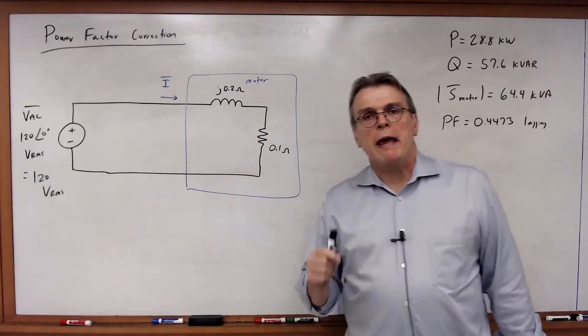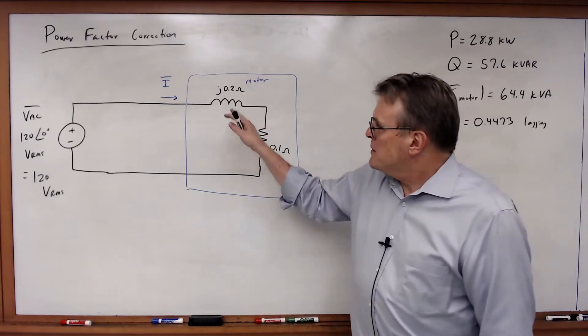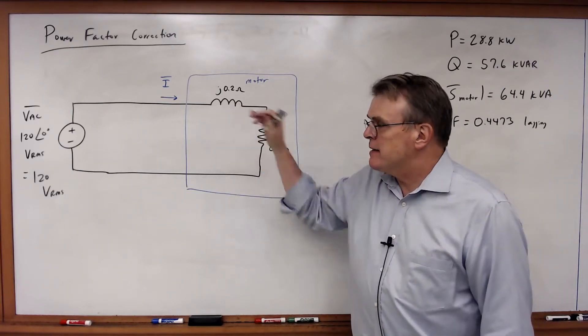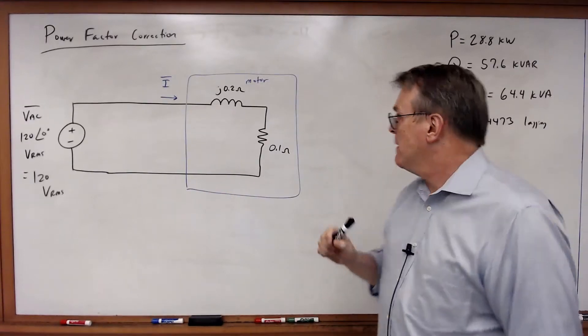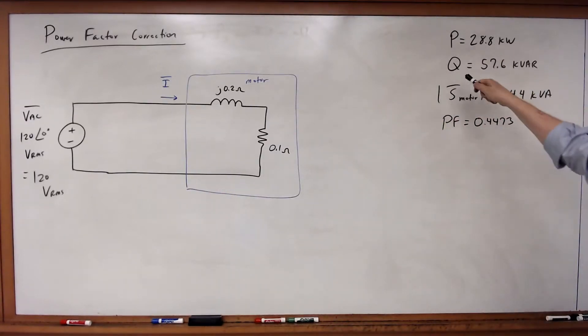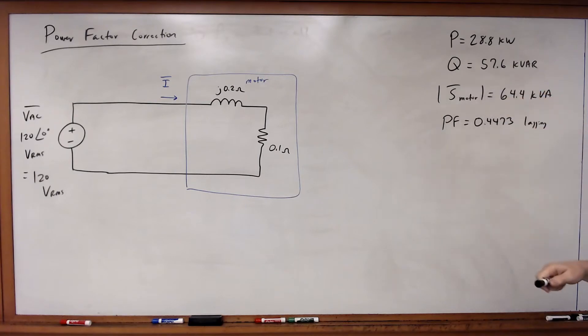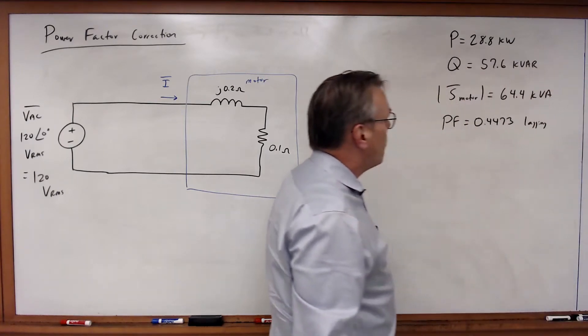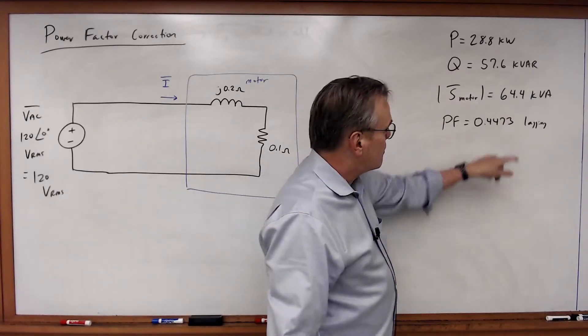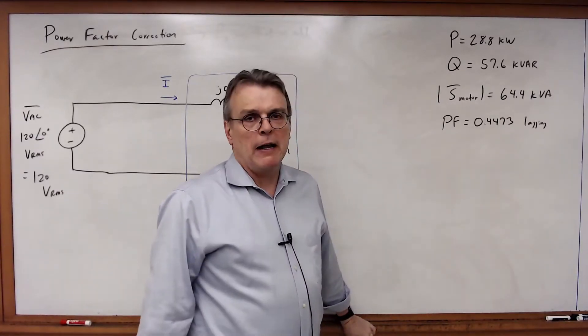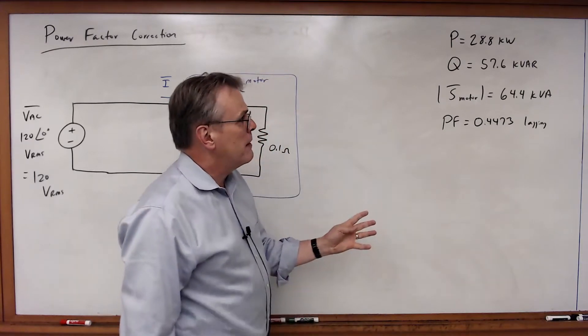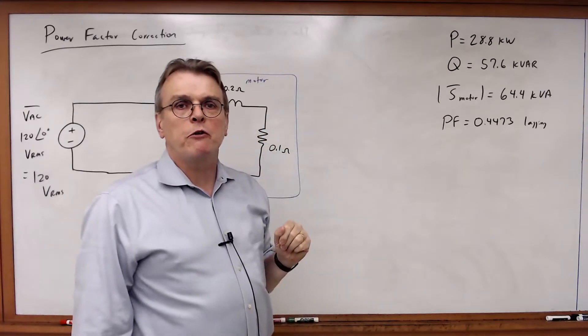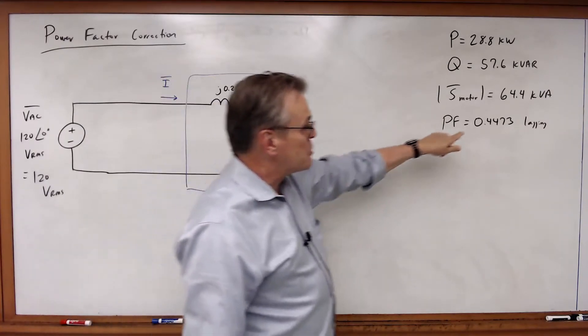Last time we looked at an example where we had a motor and this complex load had a real and an imaginary portion, where we had a real power of 28.8 kilowatts, a reactive power of 57.6 kilovars, with an apparent power of 64.4 kVA and a power factor of 0.4473 lagging. The power company is going to charge you for having a power factor that's too low.